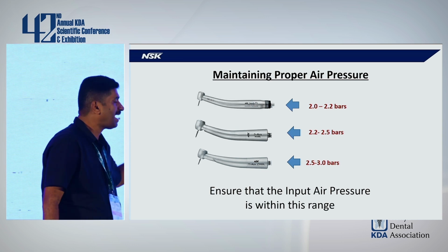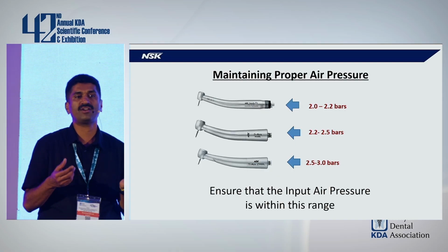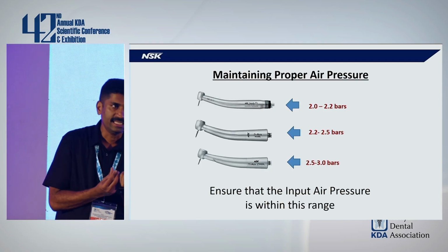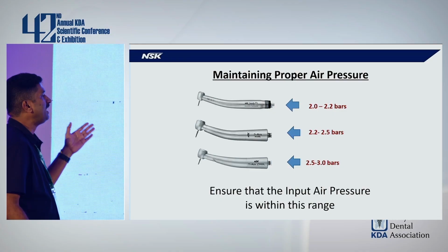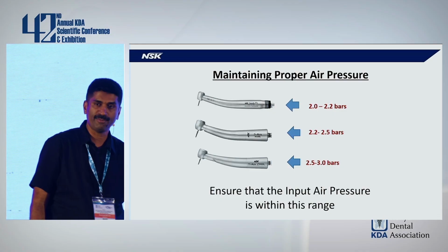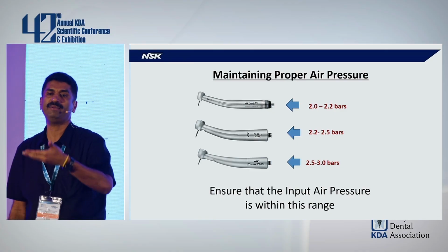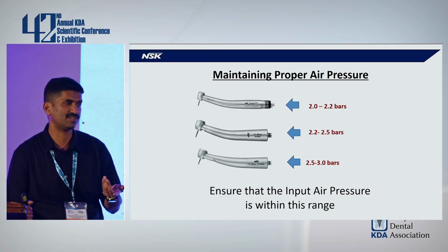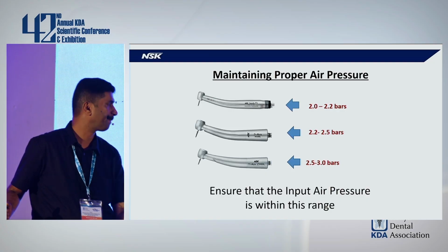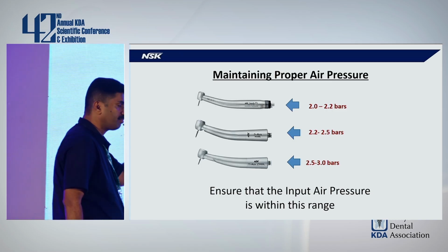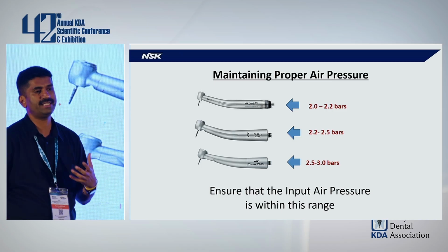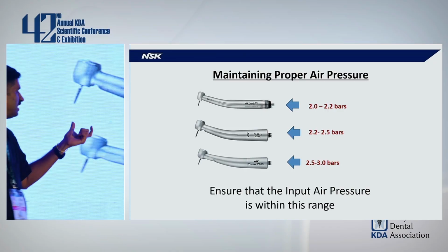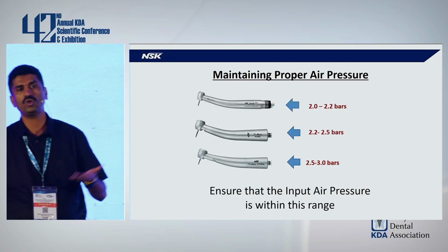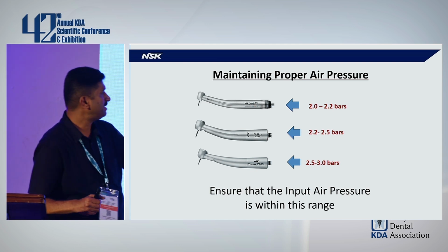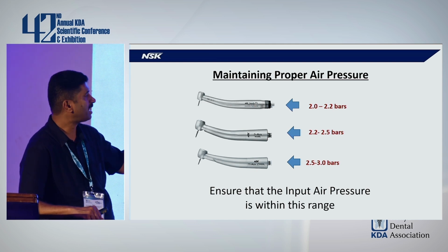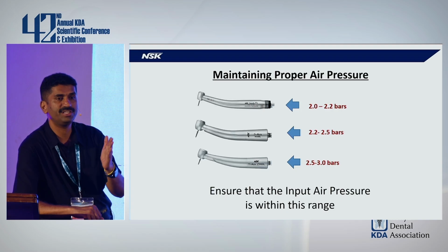Now, if you're using a higher-end handpiece, in the sense there are optic handpieces which need a coupling, there you may go up to a range of 2.5 bars. Such handpieces can withstand a little bit higher pressure, which is 2.5 bars or 0.25 MPa. And for premium handpieces from NSK, which we call titanium handpieces, the Z series, you can go up to 3 bars. But for the basic, most common handpieces, we recommend you maintain the air pressure within 2.2.